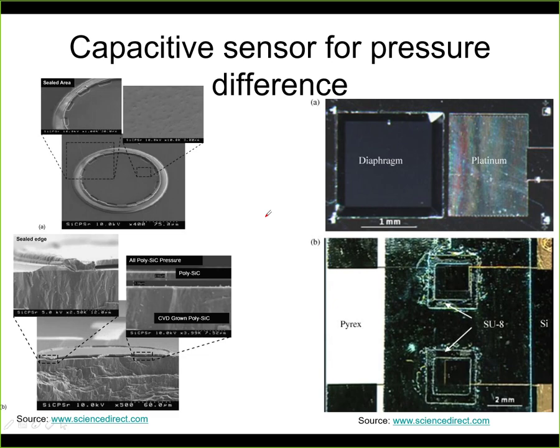Now here is such an example. It's still the capacitive sensor for pressure, but now it's produced on a chip. So I've found here two versions that we can discuss. The one on the left, it has a round diaphragm, so we can see the diaphragm over here. You can see the scale, so this is 75 micrometers, so it can be very small. The size of the chip is typically something like 5 by 5 millimeters, approximately, including the terminals.